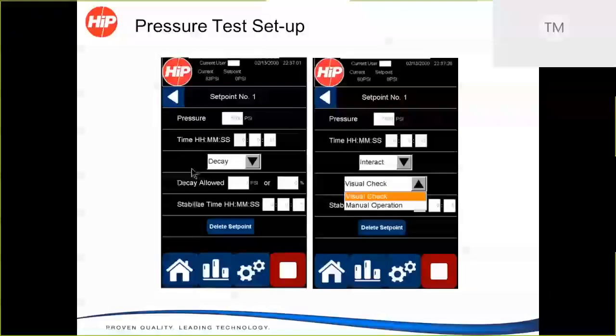And this decay test will allow you to enter either an amount of PSI or a percentage of the max pressure rating that, if you exceed that on a leak decay test, then we'll classify that test as failed, and we'll finish the test, and we'll notify the user that the unit under test did not meet the decay test.